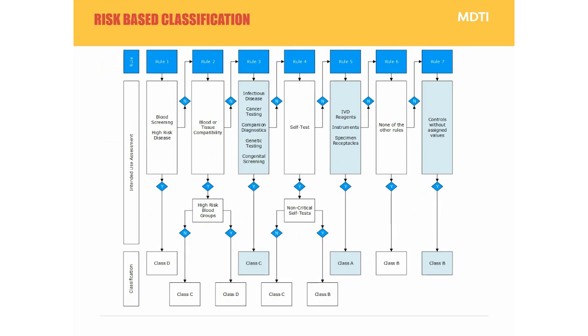That's a big change, and we would really advise you to engage with a notified body as soon as possible to start the discussion and selection process if you don't already have a relationship with one. Conformity assessment is based around 7 rules, highlighted in this flow diagram. As you can see, there aren't very many outcomes that lead to designation of a product as a Class A device. Really, that only happens under Rule 5, where we're talking about reagents, instruments, and specimen receptacles. So if you're falling outside those definitions, rules 1, 2, 3, 4, 6, and 7 are going to apply to your product, and you're going to need that notified body involved.